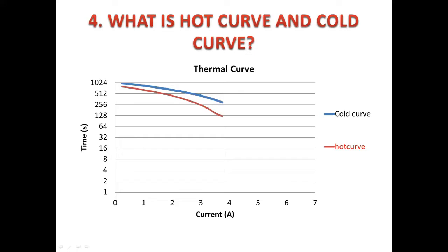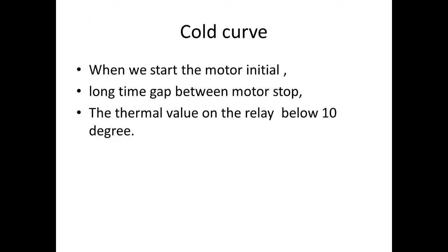Next, about hot curve and cold curve. What is hot curve and cold curve? Depending on the motor temperature, when we start, the relay follows either the thermal hot curve or cold curve. When we start the motor initially — that is at the time of commissioning or when you return from maintenance for one or two days — this is considered as an initial start. The relay will follow the thermal curve in cold curve.